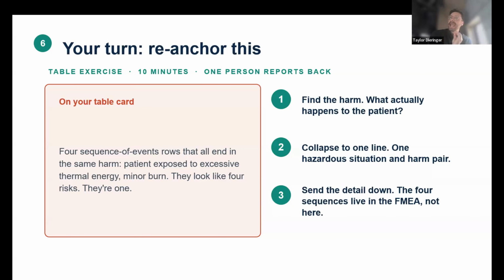So what you're saying is that you have seen that they haven't used clinical trials as a means of validating the effectiveness of a risk control measure. Is that correct? No, they've used it and they haven't documented it in the risk management file. Oh, I see. They'll say the clinical evaluation report is a validation method, which drives me crazy because, in my view, and I've had big internal debates about this, the clinical evaluation exercise and report is not itself the validation. It talks about the validation. The actual validation is to say, this risk control measure is good, I've defined it and now I've checked it in clinical studies. For me, that is the validation. And very often, let's say 50% of the time, it's not documented.